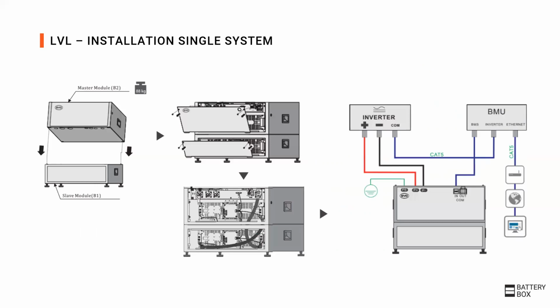For the installation, the upper and lower battery module are stacked on top of each other. Unlike the premium HVS, HVM, and LVS, the LVL requires some internal cabling. Therefore, the cover is removed. Then the cabling can be done. It is important to make sure not to make a short circuit and to connect all cables correctly and according to the manuals.